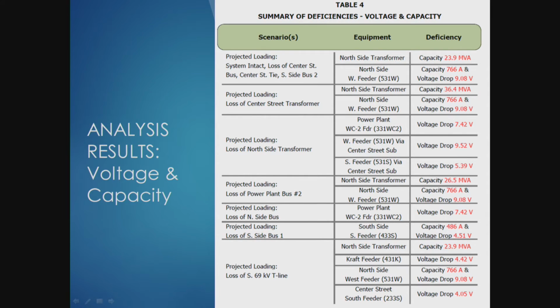But when we start adding the loads over the next 20 years, as you can see here, the north side transformer is overloaded. There's a circuit on the north side substation that delivers power up into the far northwest area of town, and that circuit runs into some capacity issues. So basically, when you start getting into the N-1 contingency, or the loss of this piece of equipment, and having to backfeed it, those conditions worsen, as it would indicate here.